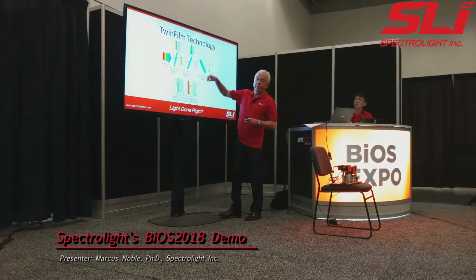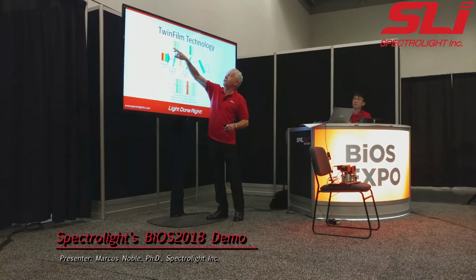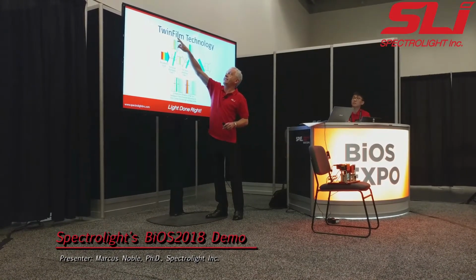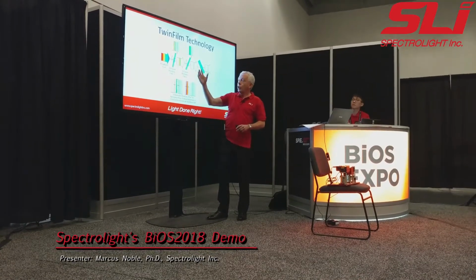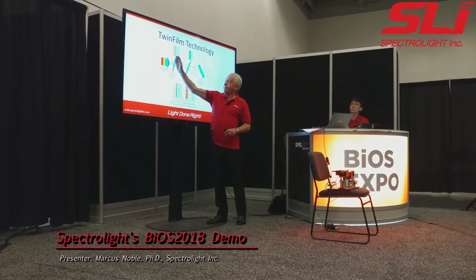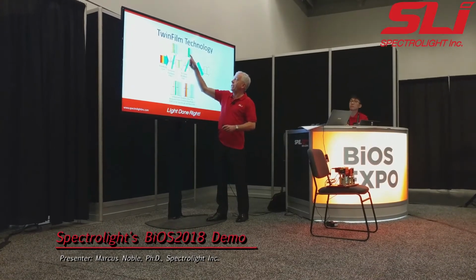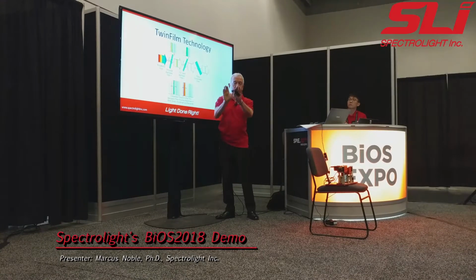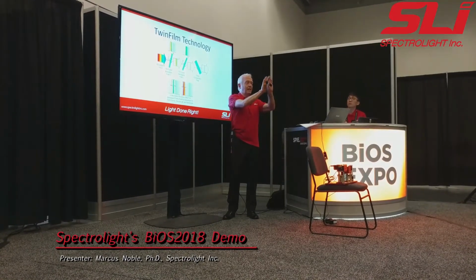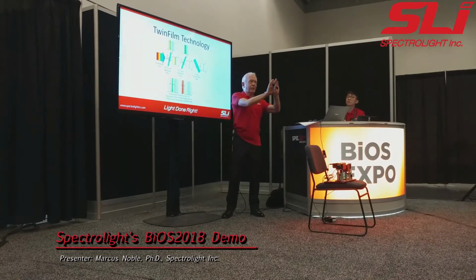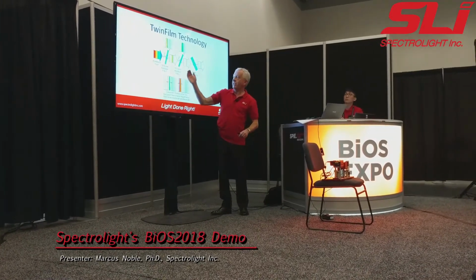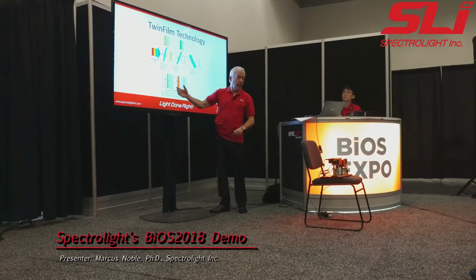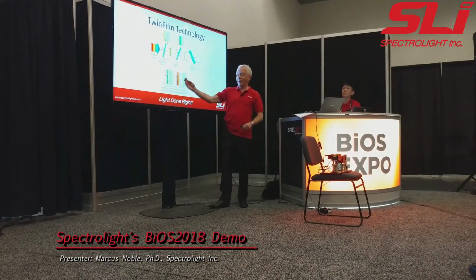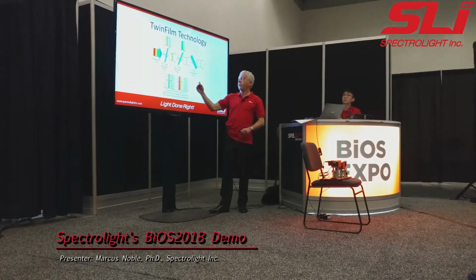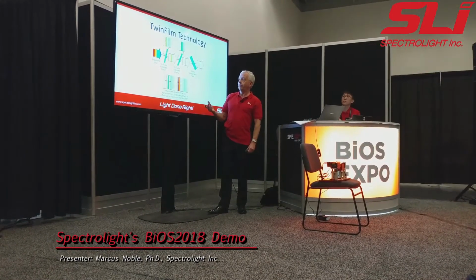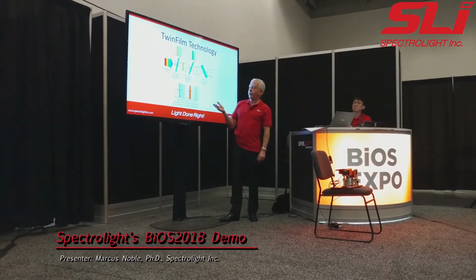So if you take one bandpass filter, plot the transmission against wavelength, you've got this standard narrow band. If you tilt that filter, you'll move that band. Now if you take two of those filters, I've now a way to set the bandwidth and to move the transmission. So by moving them relative to each other, I adjust the bandwidth, and then moving them in a concerted way, we sweep the wavelength. So it's a very, very simple, it's patented now, but it's a very simple optomechanical device.